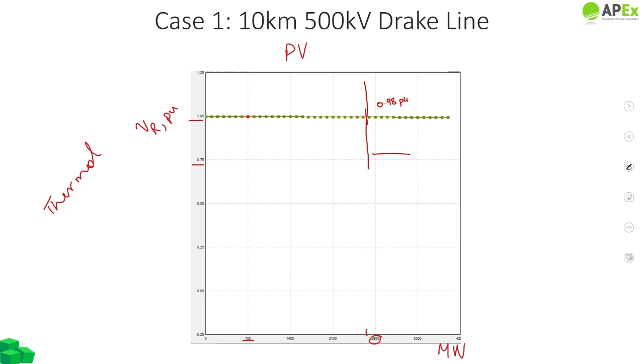If you recall from the previous slide where I asked participants to remember the thermal limits of a Drake conductor, it has a thermal limit at around 2700 megawatts. If we try to locate 2700 megawatts here, drawn with a red line, we can see that even beyond the thermal limit, there is no significant drop in the receiving end voltage. This implies that for short lines, voltage stability isn't the primary criteria—the factor limiting the flow of power for short lines at high voltage would be the thermal limit, which would be the binding constraint here.